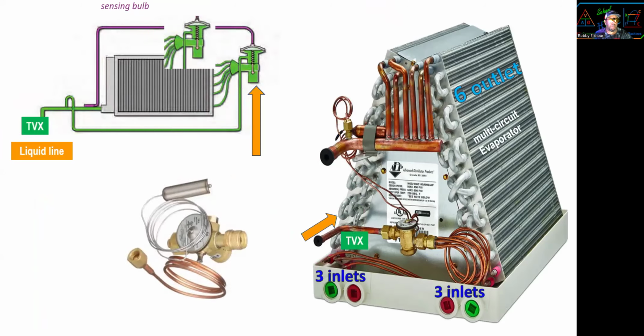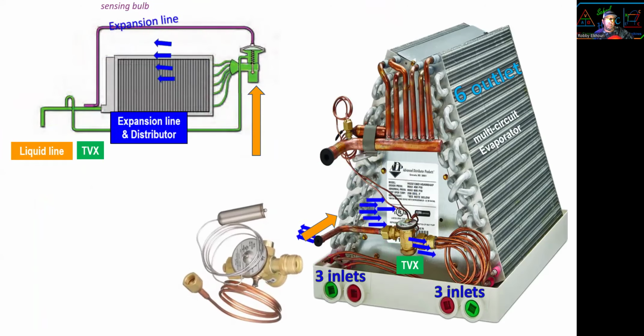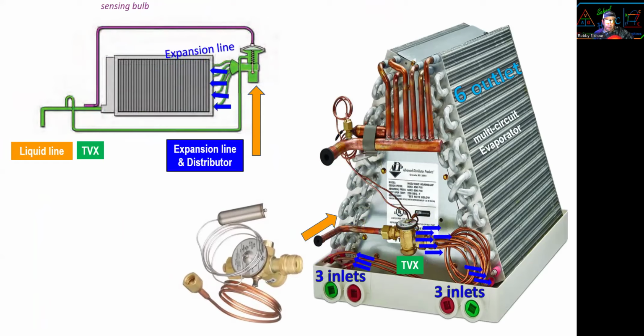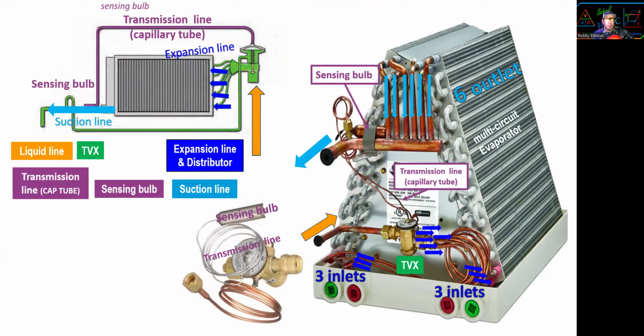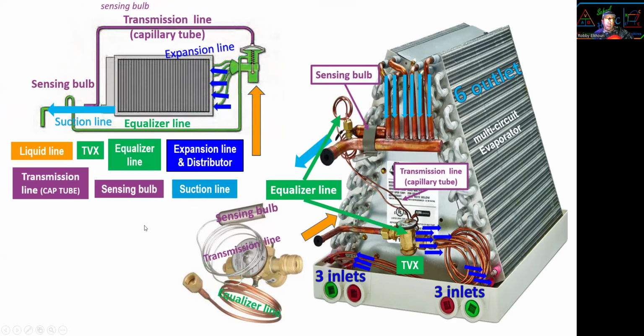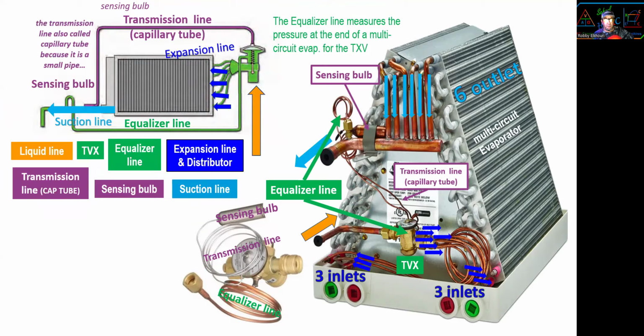Alrighty, now liquid line in, TXV, expansion line and distributor, 6 in, suction line, 6 out. All right, now with the transmission line, sensing bulb, transmission lines, sometimes they also call it the cap tube, the equalizer line reads the pressure at the end of the evaporator. The equalizer measures the pressure at the end of the multi-circuit evaporator for the TXV.